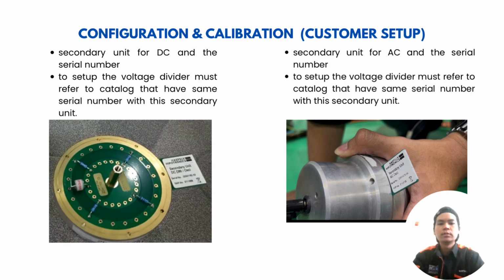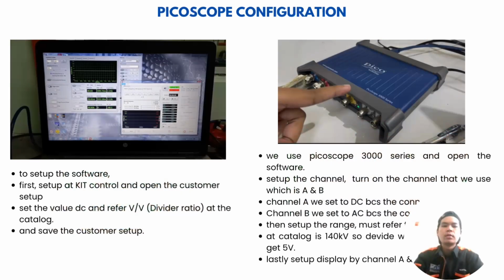Next, the slide shows the calibration step setup for both DC and AC measurement. The voltage divider must be configured using the catalog with the matching serial number to ensure accurate and reliable measurement results. For the PicoScope setup, we use the PicoScope 3000 series software. Channel A is configured for DC measurement, while channel B is configured for AC measurement. The voltage divider ratio and measurement range are set according to the catalog before saving the custom setup.